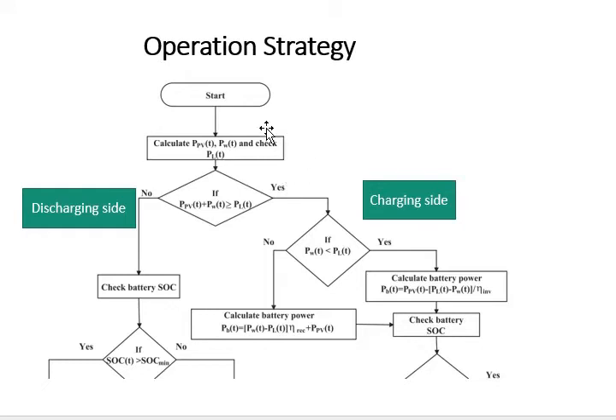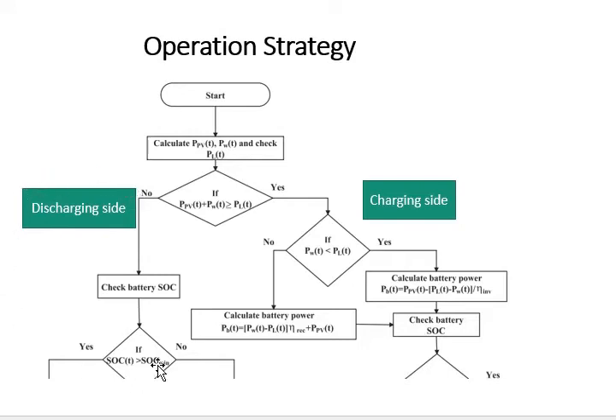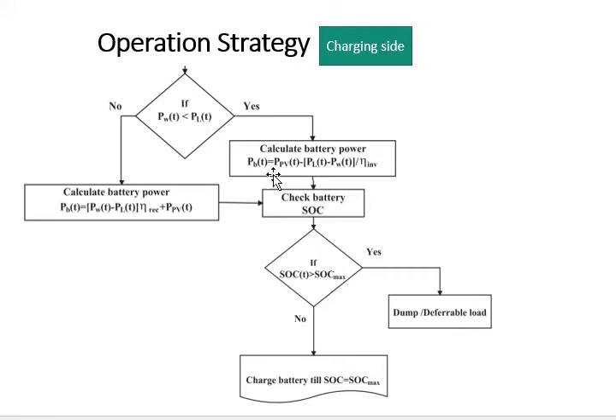The simplified steps of the operational strategy are as follows. First, PV power, wind power, and load profile are taken at time t. Then it checks whether the renewable energy generated is sufficient and surplus to meet the load demand. If yes, proceed to the charging side of the flowchart. If not sufficient, proceed to the discharging side. If power from wind turbines alone is enough to supply load demand, the remaining power from solar and wind can be fed to the battery bank, and the battery power in this case can be calculated accordingly.